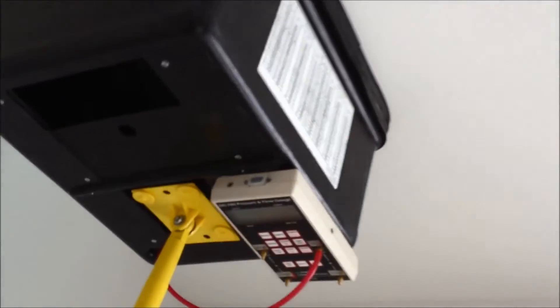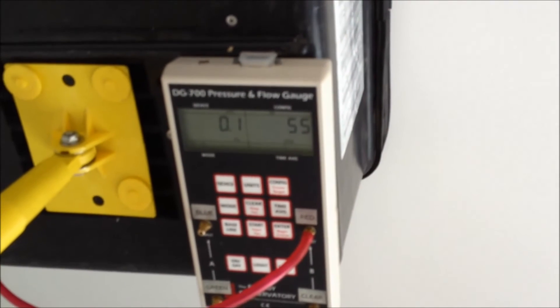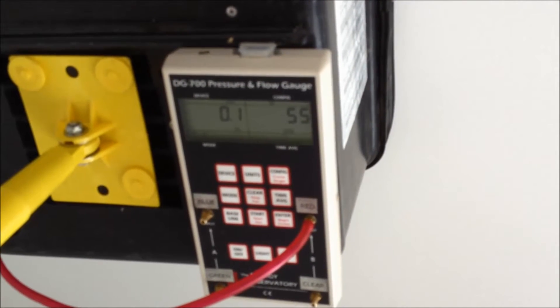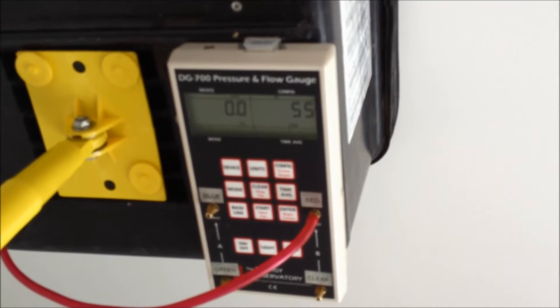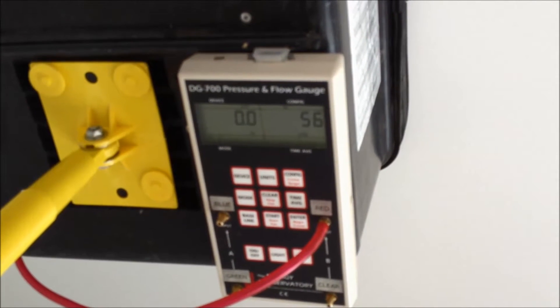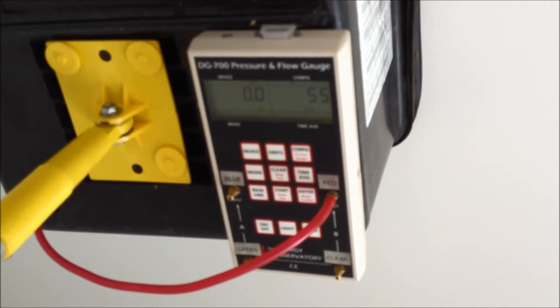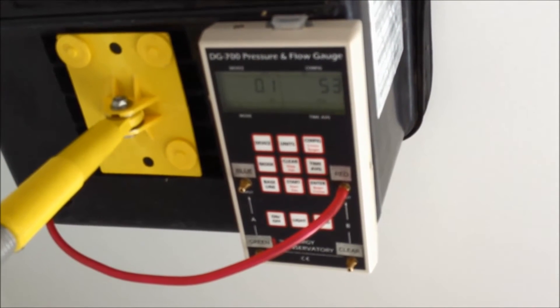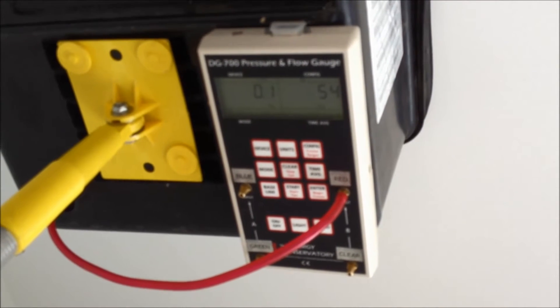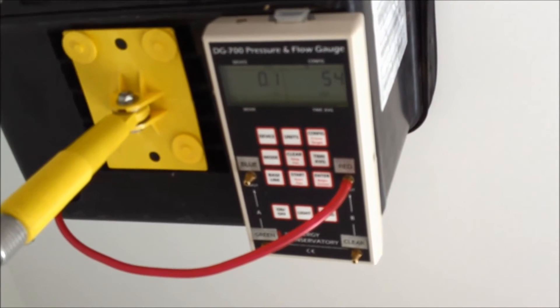If you come over here and look at the gauge, you can see we're at 54 CFMs, 55 CFMs. So this fan is working properly. Remember, Energy Star version 3 requires that a bathroom that has a shower or a tub in it has to be at least 50 CFMs. So this is probably a 75 or 80 CFM fan that is blowing at 50 to 54, which is normal.